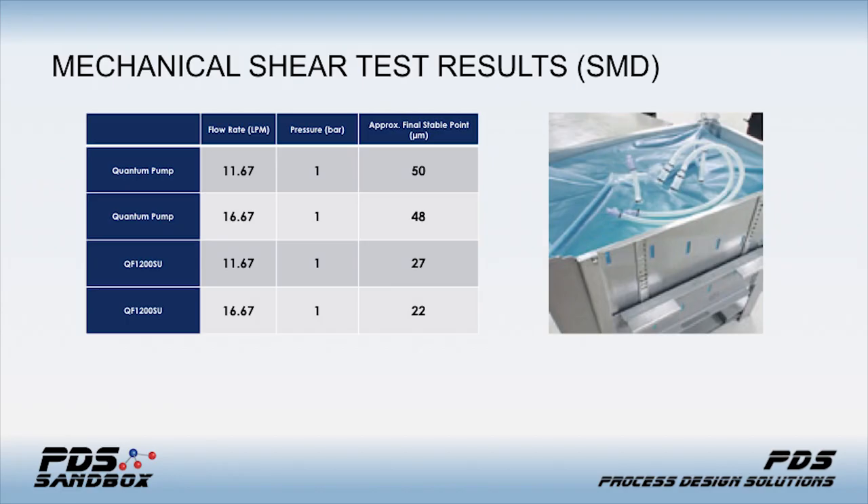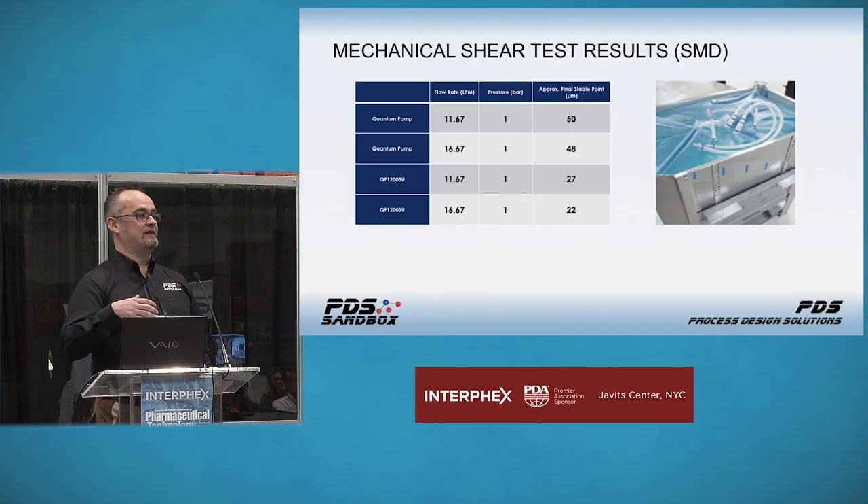We ran multiple pressures. At one bar pressure at 11.67 liters per minute — why 11.67? That was the nominal flow rate established through testing by Levitronix in Zurich, so we use 11.67 as an industry benchmark for comparative testing of pumps sized and scaled to 0–20 liters per minute. Looking at the mechanical shear results on the next slide, both pumps started at around 70 microns and then tapered off. Once they're stable within five percent for up to 20 minutes, that's when we consider we've imparted as much mechanical shear as possible.